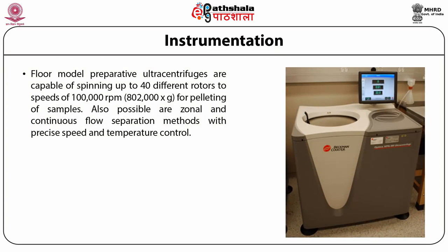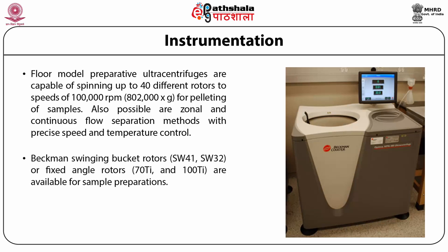The Beckman Preparative Ultracentrifuge is capable of spinning up to 40 different rotors to a speed of 100,000 rpm — that is 800,000 g — for pelleting of samples. It also enables zonal and continuous flow separation methods with precise speed and temperature control. Beckman swinging bucket rotors or fixed angle rotors are available for this type of sample preparation, and this is the most widely used preparative ultracentrifuge.